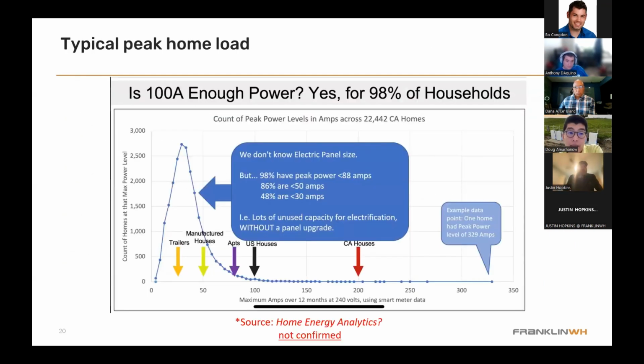With a 100 amp service, someone might say they have a modern home with a lot of electronics and need 200 amp service. But in reality, their peak power consumption will most often be way less than 100 amps. Even on a 400 amp service, on a 4,000 to 5,000 square foot home, they'll still be under 100 amps of power.